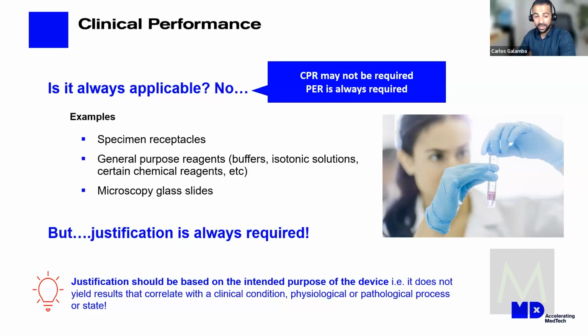I know, and I agree, Johnny. And for me, even though from a notified body perspective it's not considered high risk, if the swab doesn't work, your assay is not going to work. So if you're not collecting enough DNA from the patient to be able to amplify that DNA and then test for the virus that patient has, and there's an issue with the swab, that issue needs to be investigated for sure. But from a regulatory perspective and the approval at the notified body, they usually pick that up via the assay, which is the thing that links the patient and the result. And then the notified body will ask questions on the validity of that swab, but by virtue of the assay, of the test that swab is used with.